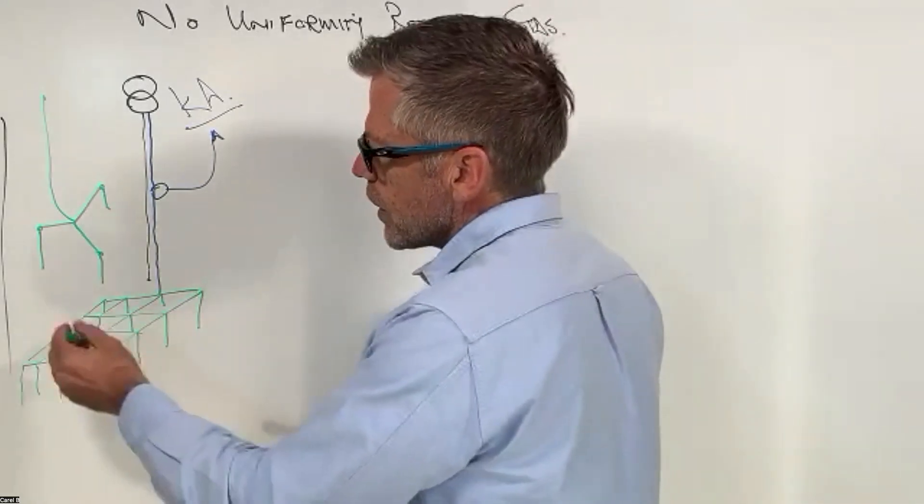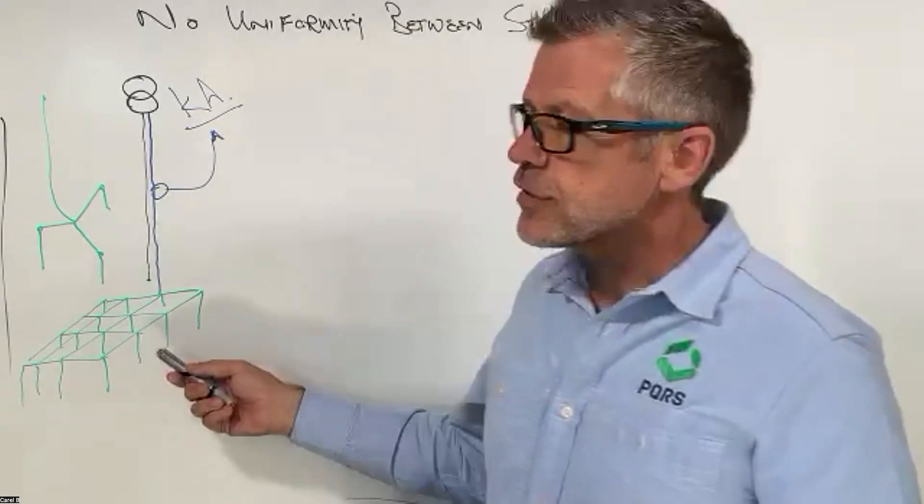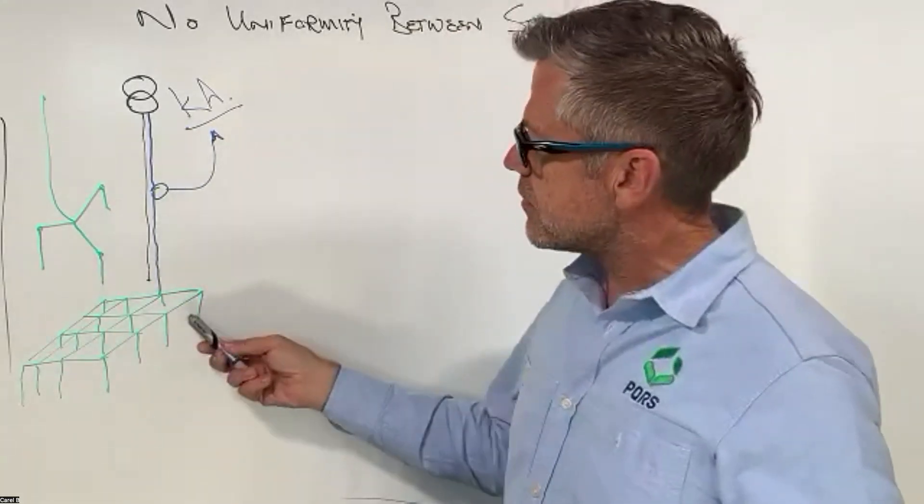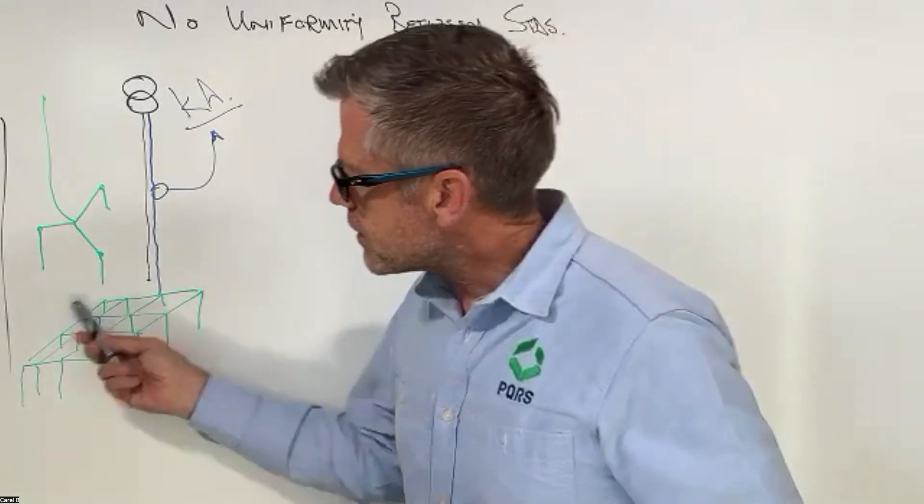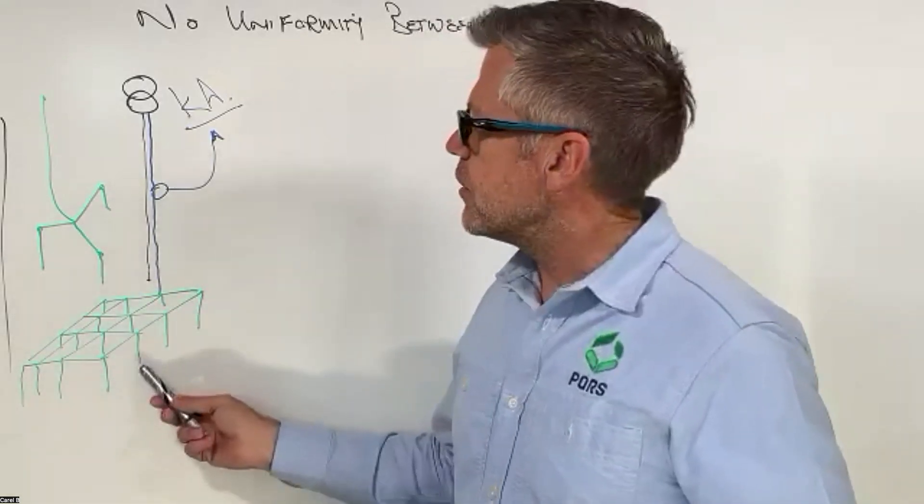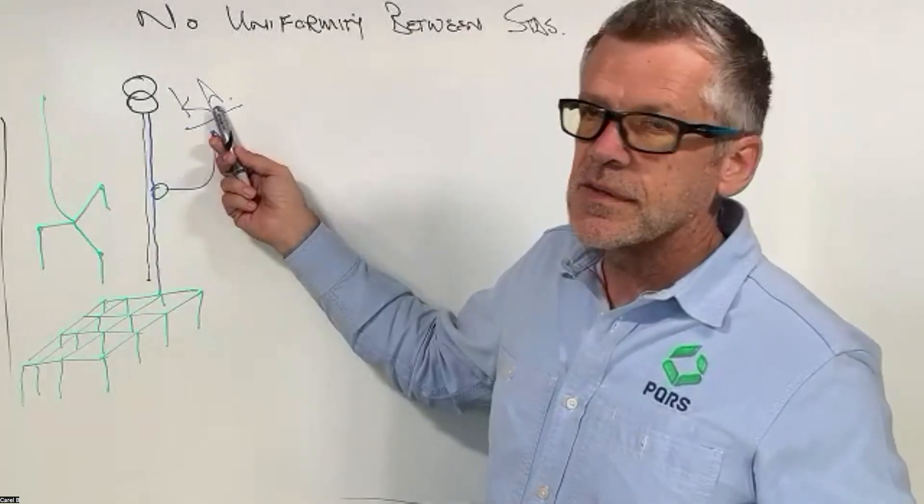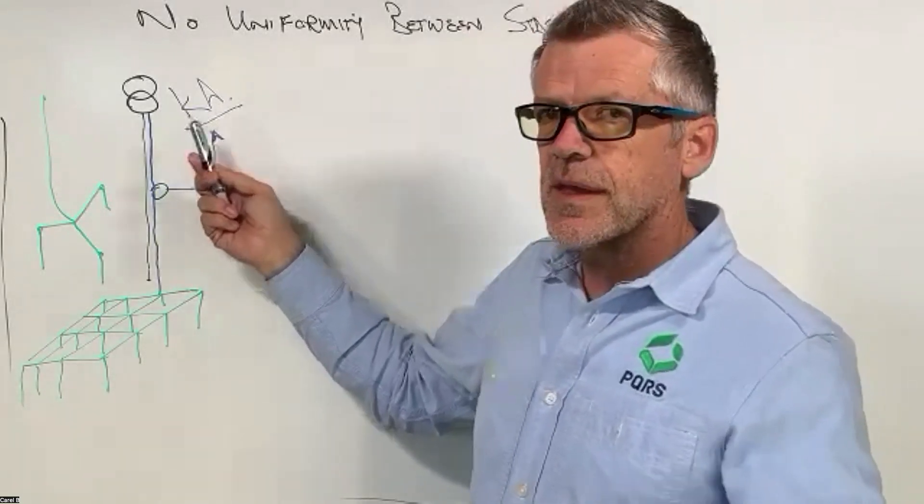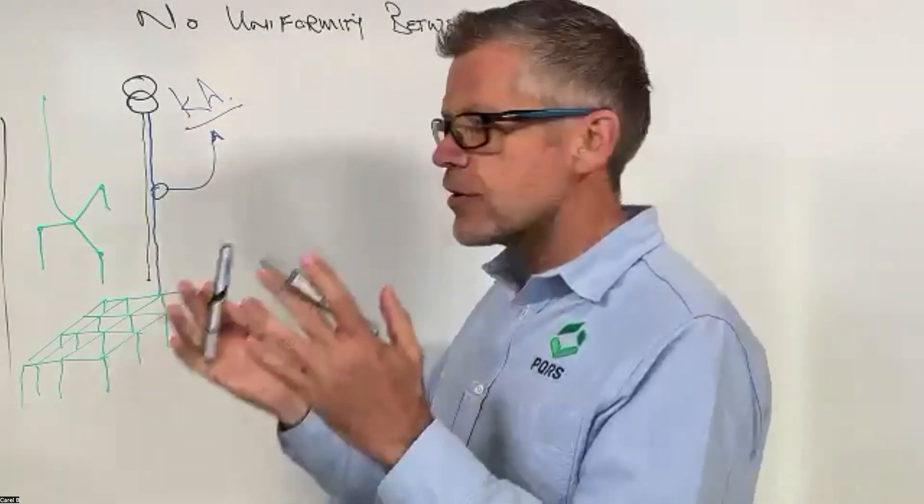And they come to where they want to build the substation or where they need to put the earth mat in, and they measure the soil resistivity values. And that tells them how big this thing has to be in order to dissipate the amount of fault current coming from the transformer in the event of a fault condition.